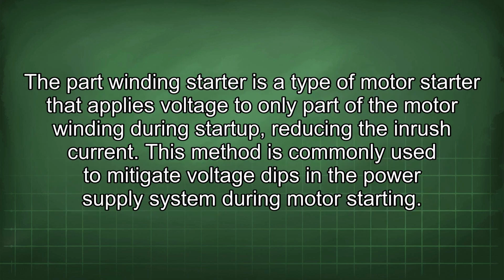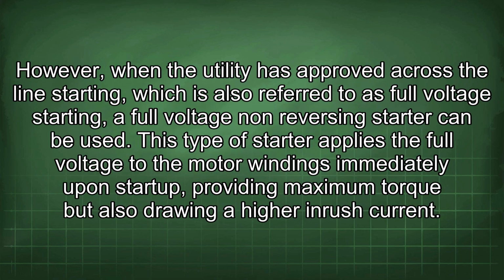The part winding starter is a type of motor starter that applies voltage to only part of the motor winding during startup, reducing the inrush current. This method is commonly used to mitigate voltage dips in the power supply system during motor starting. However, when the utility has approved across-the-line starting, which is also referred to as full voltage starting, a full voltage non-reversing starter can be used.